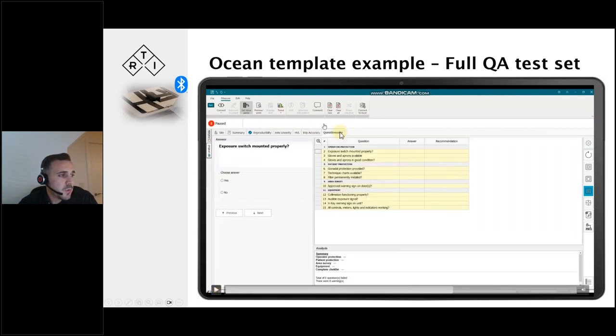Questionnaires are also helpful. As an engineer, you might have to do physical tests or checks on a system - are the covers mounted properly, is the collimation functioning, is there an audible exposure signal, is there a warning label? You can also put this into your template, meaning you can go through this sheet once you're doing your X-ray tests and have it as part of the report.